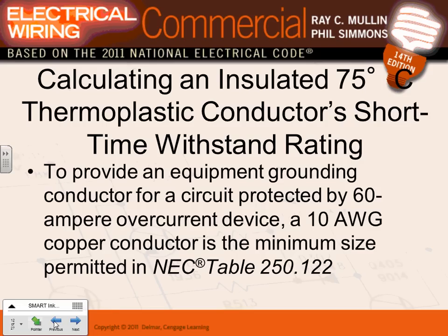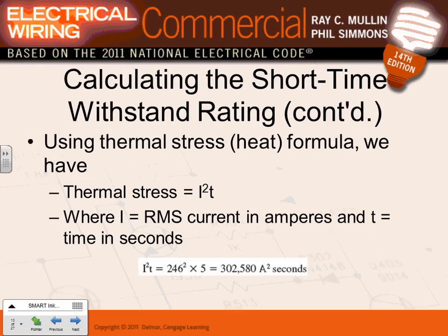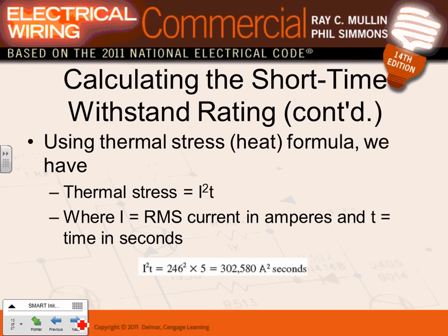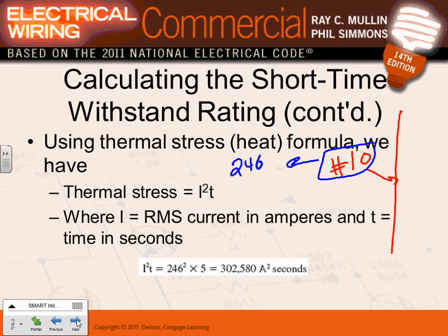Okay. Time withstand, calculating time withstand from a table. What they're doing, guys, is the same calculation, just using the formula. This is an example that they're using for you. Very easy, very simple. I have a number 10 conductor. Can you guys see this number 10 conductor? The manufacturer is telling me it can handle 246 amps.